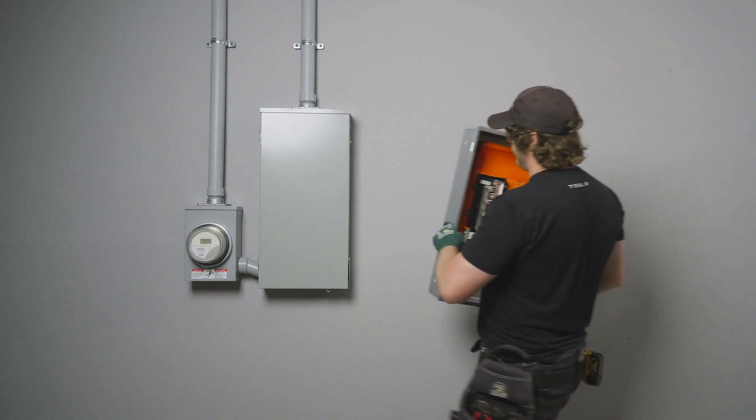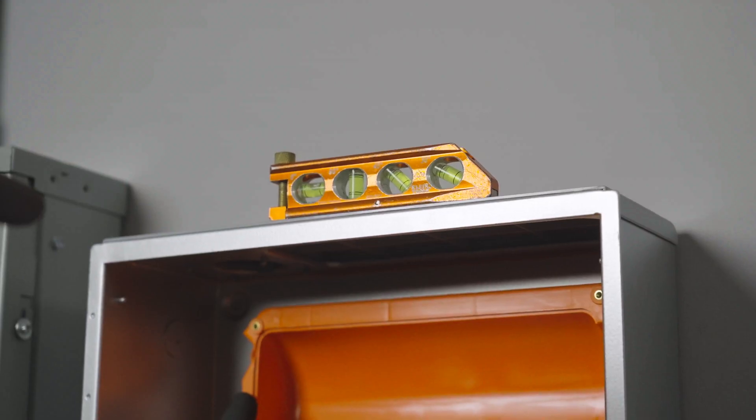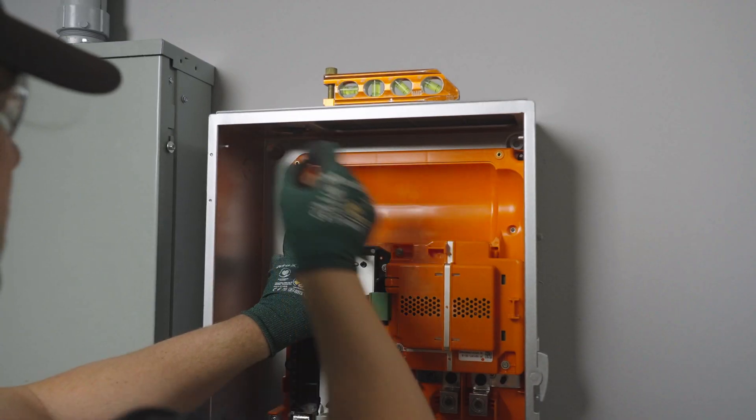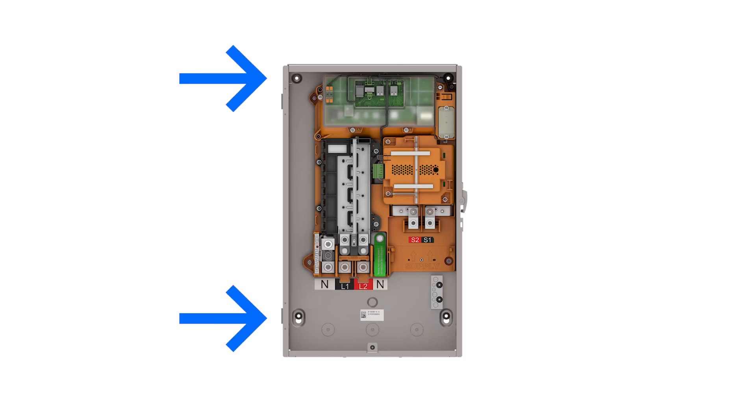After conduit knockouts have been made, hold the enclosure in place against the wall. Level the enclosure and mark the wall through each of the four fastener holes. For PowerShare Gateway, at least two fasteners must be secured to a structural member to support its extra weight.